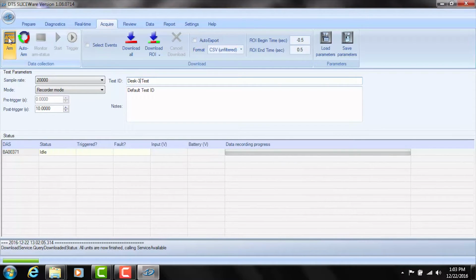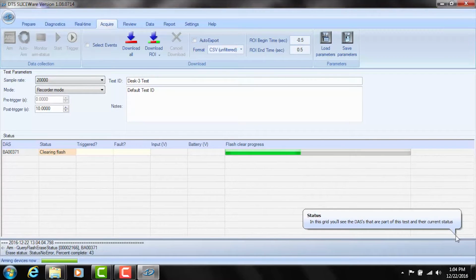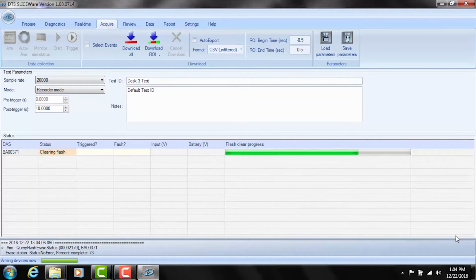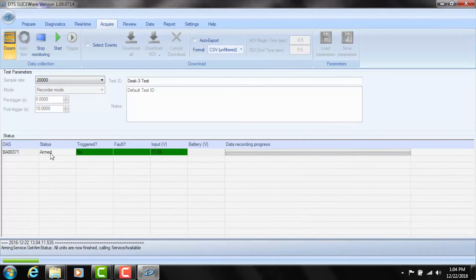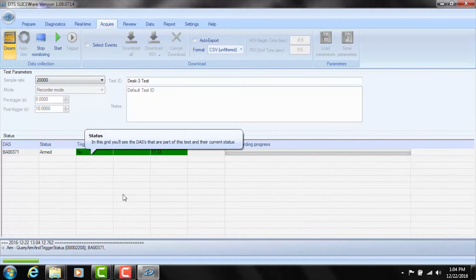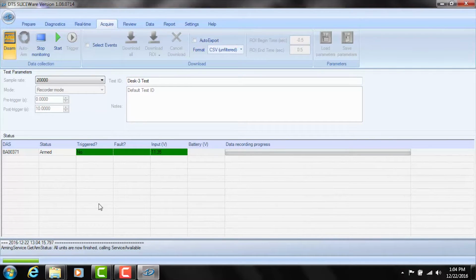I'll go ahead and go up to the top left and select ARM. And that basically prepares the slice system for data acquisition. So right now it's clearing out the flash memory of the system, and when that's finished, it'll tell us that it's armed and it hasn't triggered yet. So at this point, we could disconnect the slice system from the USB drive, and we can go ahead and connect it to our test article and connect our sensors up, and we're ready to go.